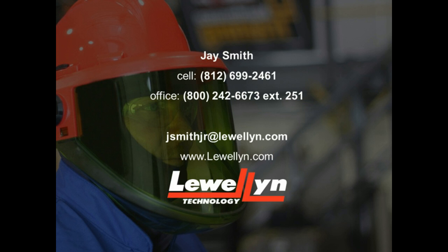Does Arc Flash clothing need to be rated in calories? Someone's saying theirs is rated in HRC only. No, you need to make sure you have a calorie rating. I would talk to your clothing vendor, especially if you're in some form of rental program. I would be very leery of equipment that doesn't have a tag with the actual rating on it. You don't want to just see HRC2, HRC4, CAT2, or CAT4 on the gear.